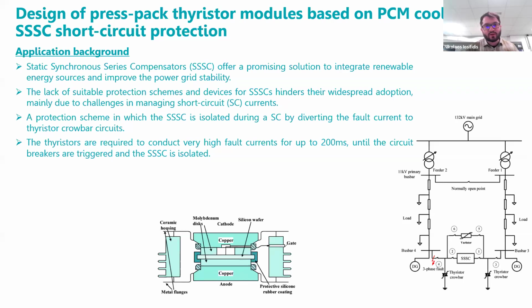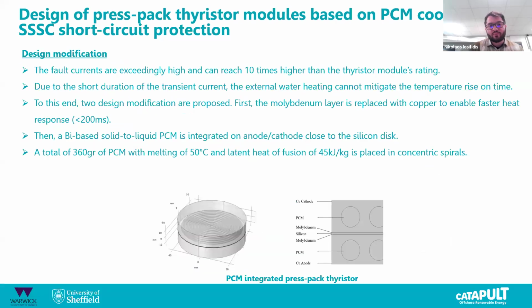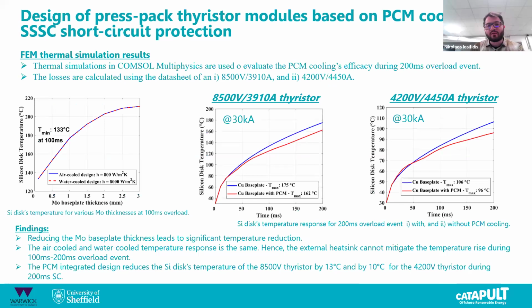So for this study, if you go to the next slide, please, we have integrated, in concentric spirals, the phase change material that has a 50 degrees C melting point and a latent heat of fusion of 45 kilojoules per kilogram. And we will be testing according to some commercial thyristor modules for 2 ratings. If you go to the next slide, please, we have simulated the thermal response over 200 milliseconds for one conventional thyristor package and one with this integrated.